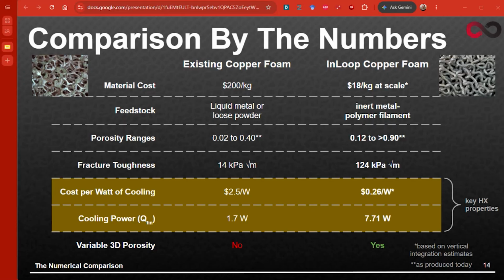When we looked at the thermal tests for our copper metal foams, we were really surprised. We set up heat exchanger experiments with different metal foams on the market today, as well as our copper metal foam, and found we could produce a heat exchanger with a better cost per watt of cooling because it removed so much heat from a hot plate. We can also provide variable 3D porosity, which is critical for certain applications in thermal and mechanical work.